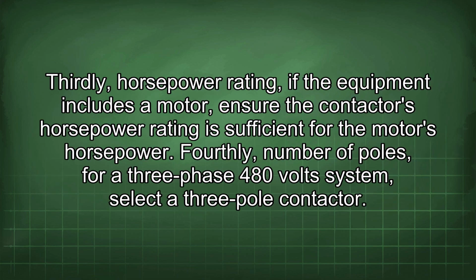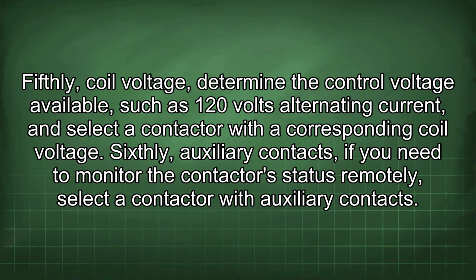If the equipment includes a motor, ensure the contactor's horsepower rating is sufficient for the motor's horsepower. Fourthly, number of poles. For a three-phase 480-volt system, select a three-pole contactor. Fifthly, coil voltage. Determine the control voltage available, such as 120 volts alternating current, and select a contactor with a corresponding coil voltage. Sixthly, auxiliary contacts. If you need to monitor the contactor's status remotely, select a contactor with auxiliary contacts.